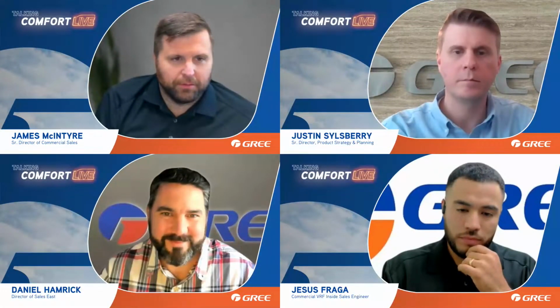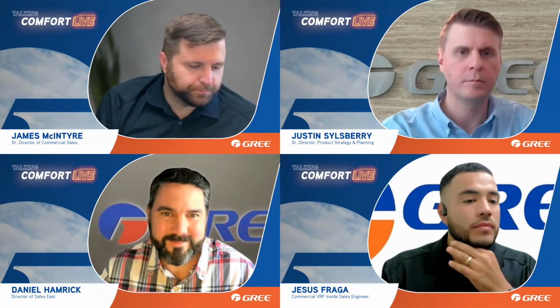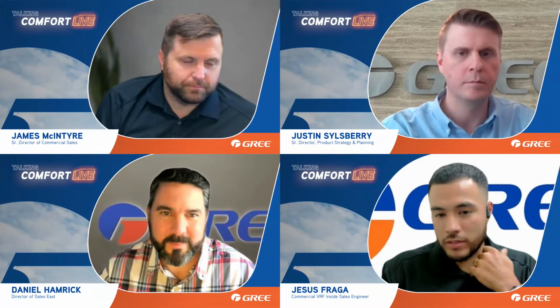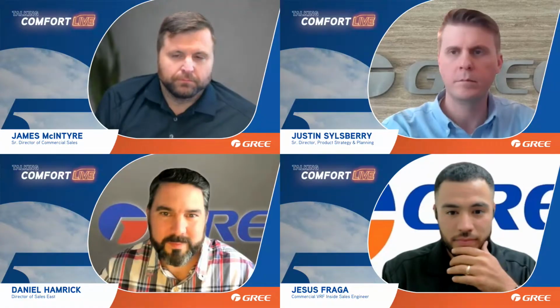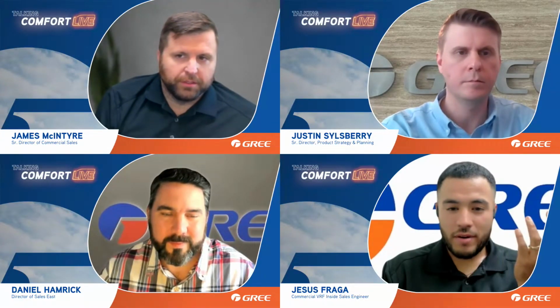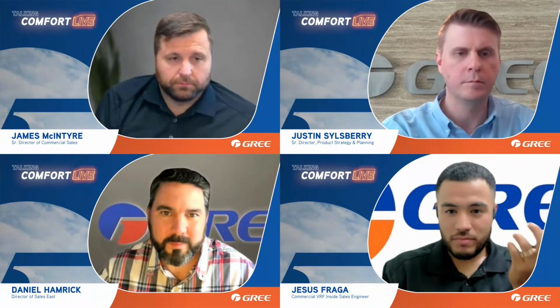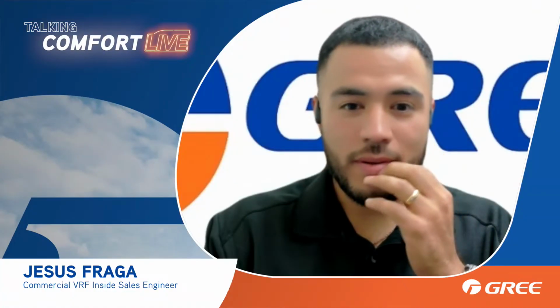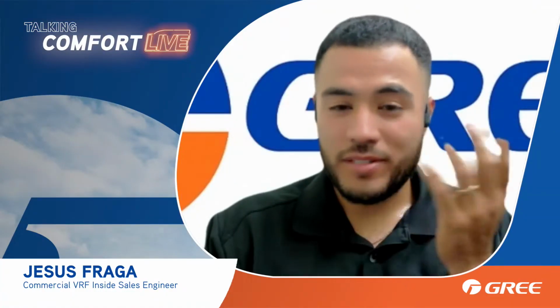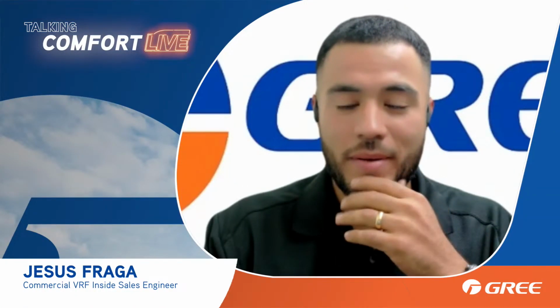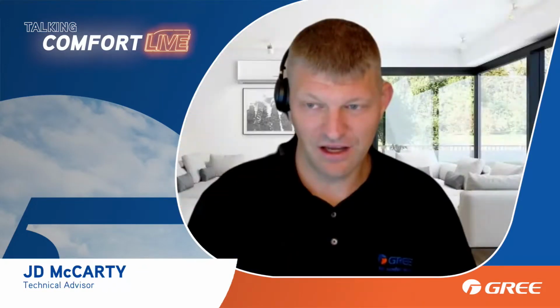If we've got a flooded evaporator coil and high amp draw, what could be causing the high amp draw if we have a flooded coil? Overcharge, maybe. Overcharge for sure. Yeah. Could it also be other items like blower wheel dirty, evaporator coil dirty, filter dirty? Just so poor airflow? Yeah. Poor airflow. High static. I gotcha.